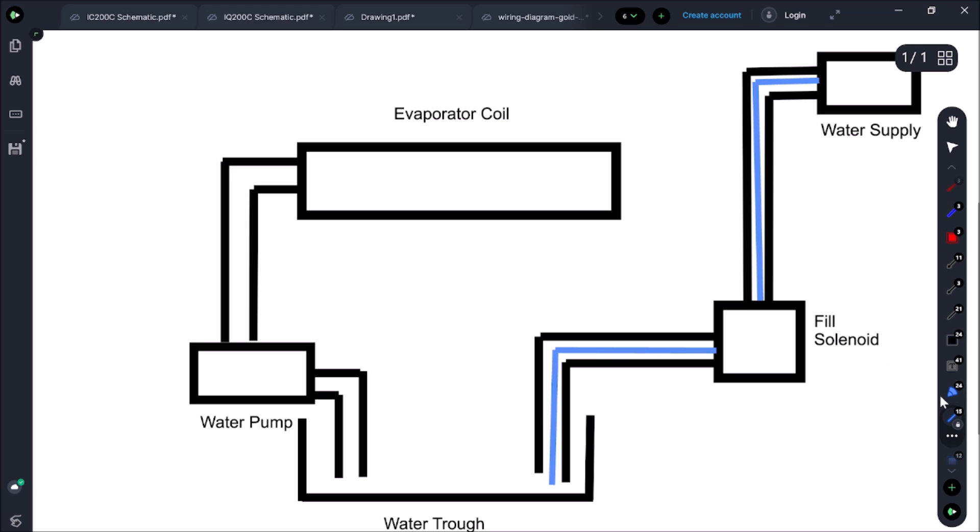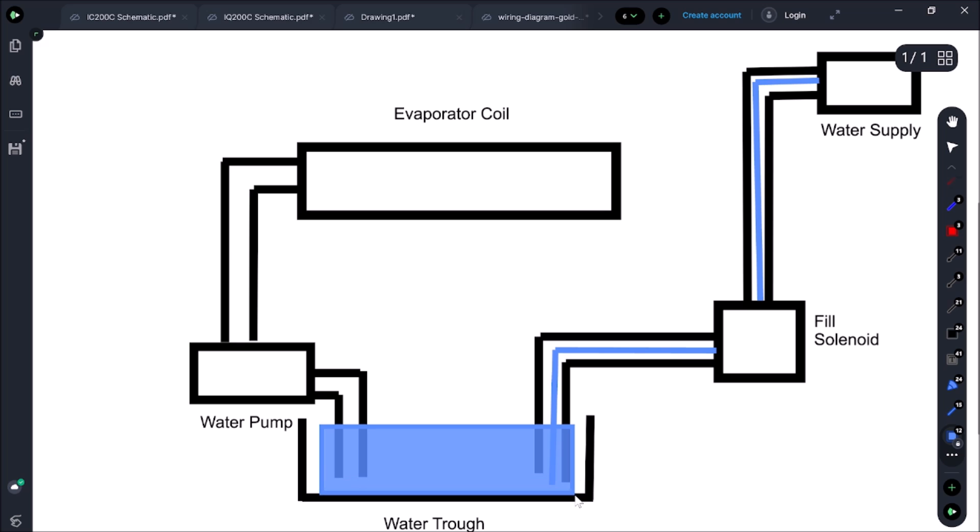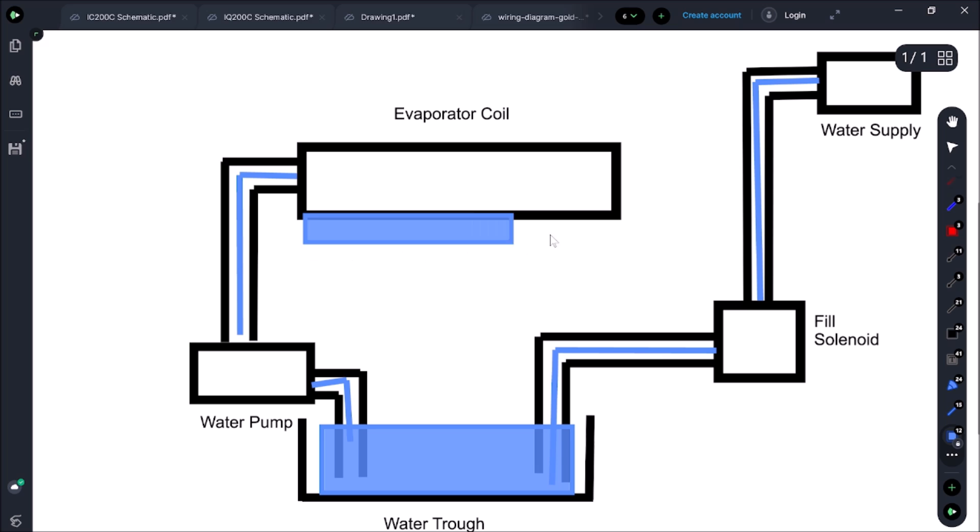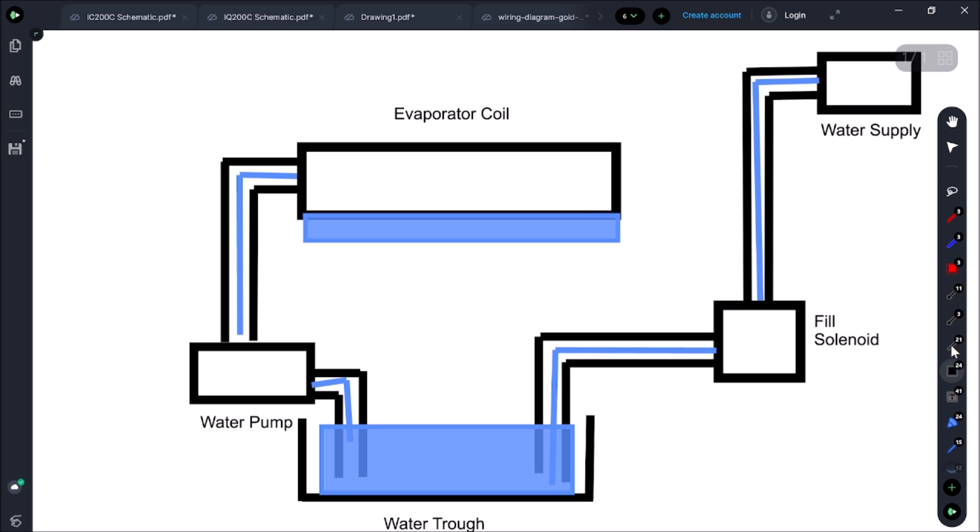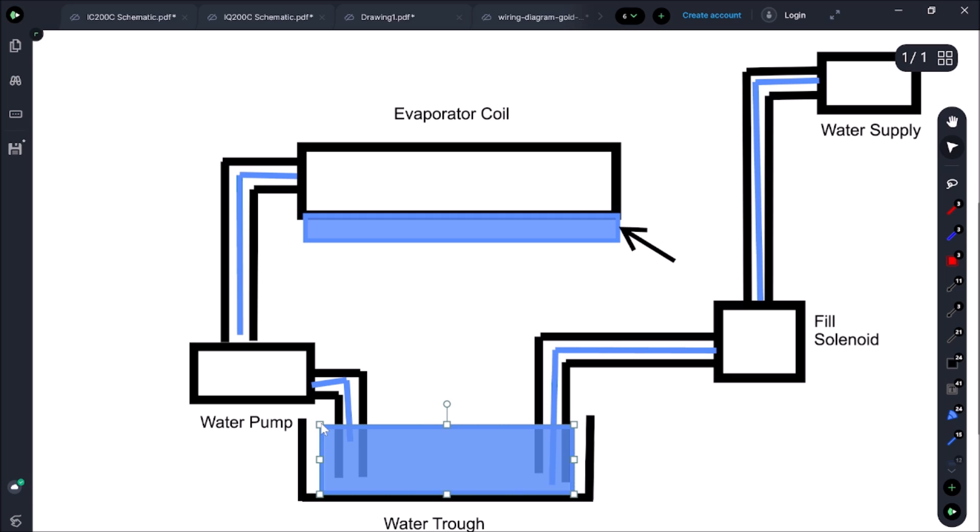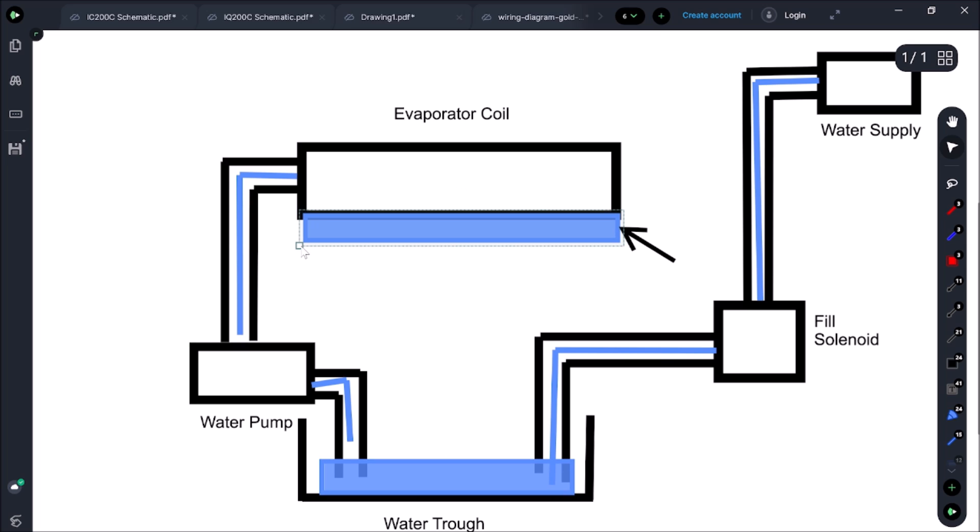Once we fill up our water trough, we're going to get suction from the pump and the pump is going to bring it up into the evaporator coil and we're going to start freezing on our coil. As this chunk of ice gets bigger, this water level is actually going to start dropping right here because we're freezing up on here and this will grow. We don't have a float switch or anything. We bring in water and we don't add in any more water throughout the cycle.